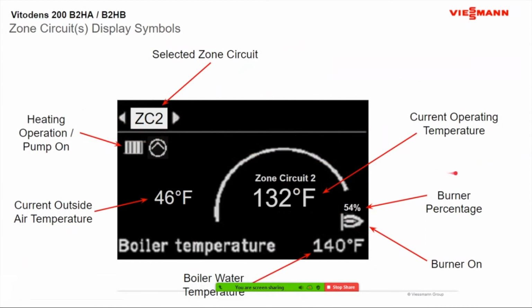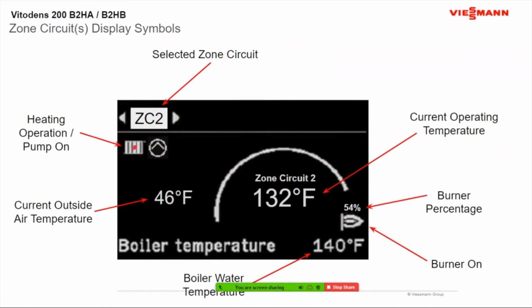So now we're looking at that interface and showing you, we're looking at zone circuit 2. Remember, we set that up for weather compensation. So what it's showing you here on the main screen is that we are looking at zone circuit 2. If you push your left or right arrow, this would bring it to zone circuit 1, zone circuit 2, or if you had zone circuit 3, you could push that arrow left or right and just keep changing your screen that way. But as you can see, we're running, so that represents a radiator. So we're in the heat mode, and then that circle with the triangle in it means that our pump is on. Right below that, we're looking at our outdoor temperature. And then over here, we're looking at our current boiler water temperature.